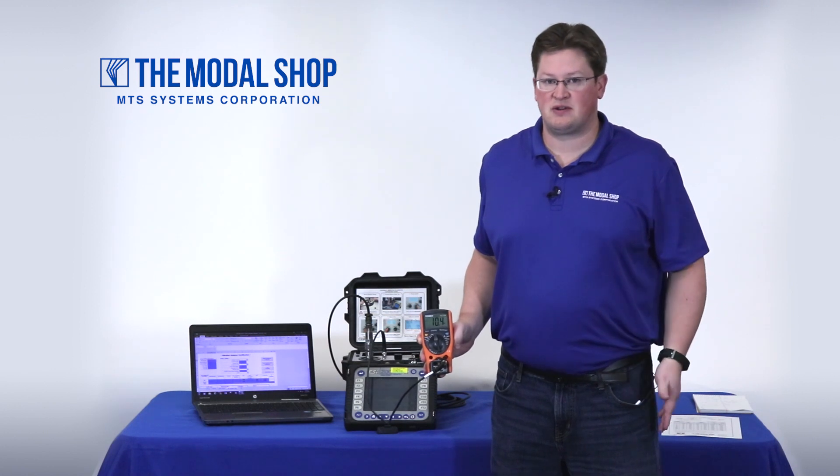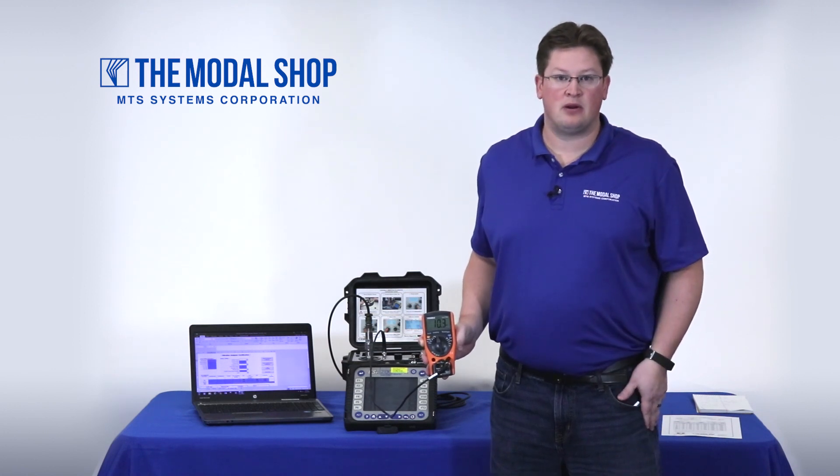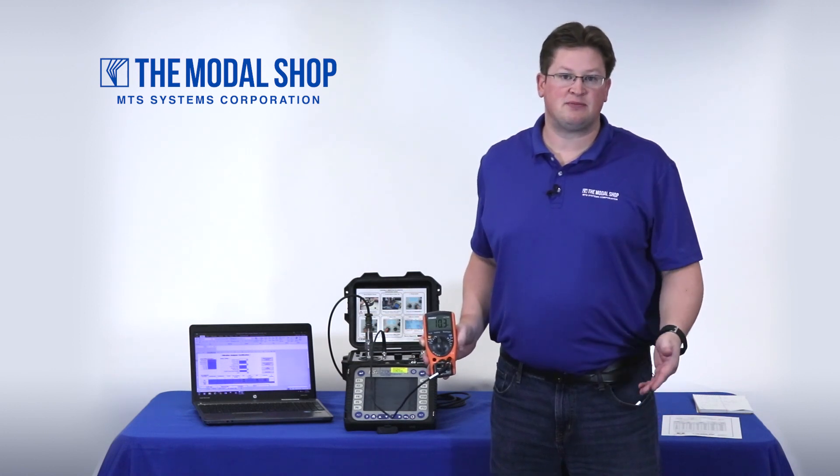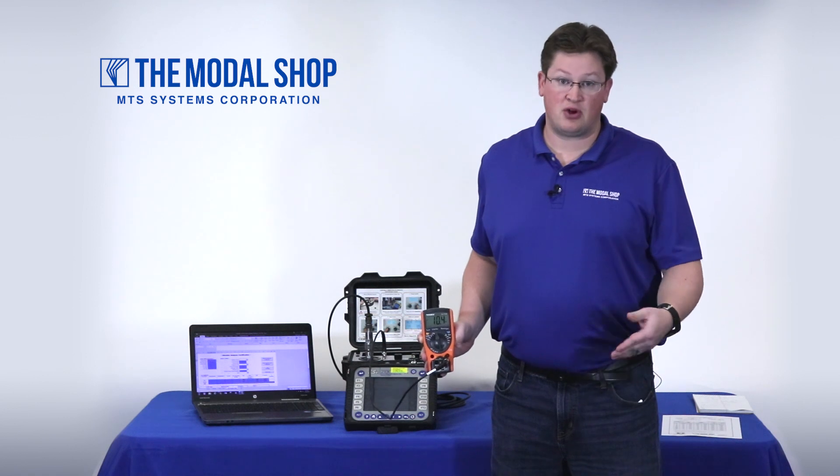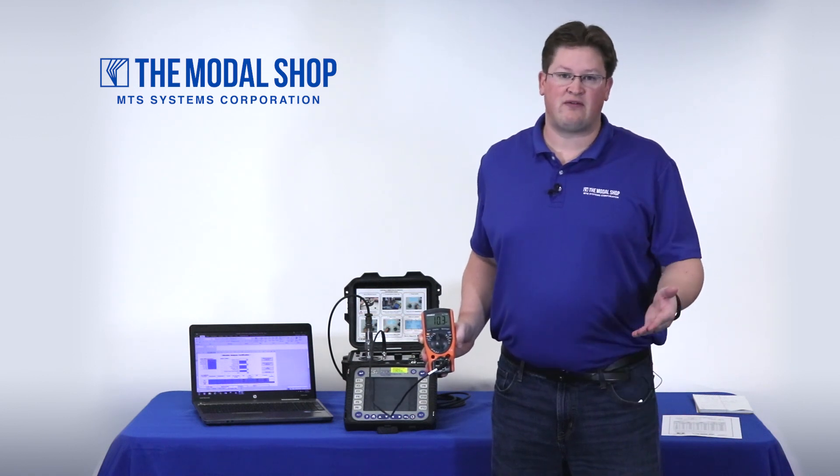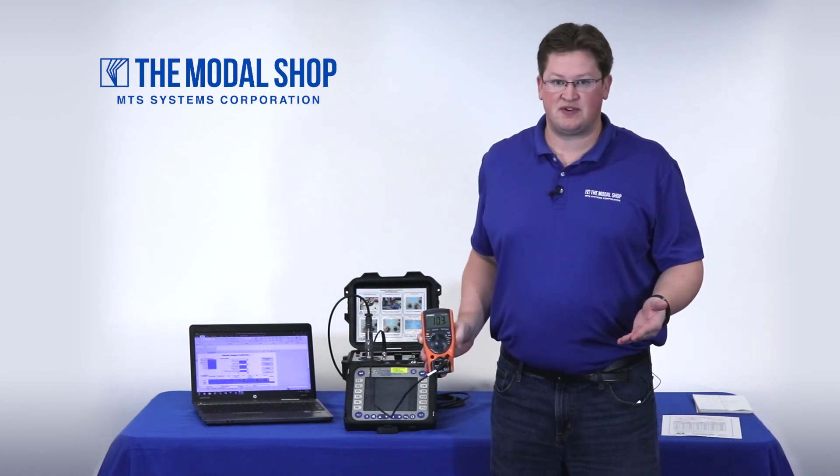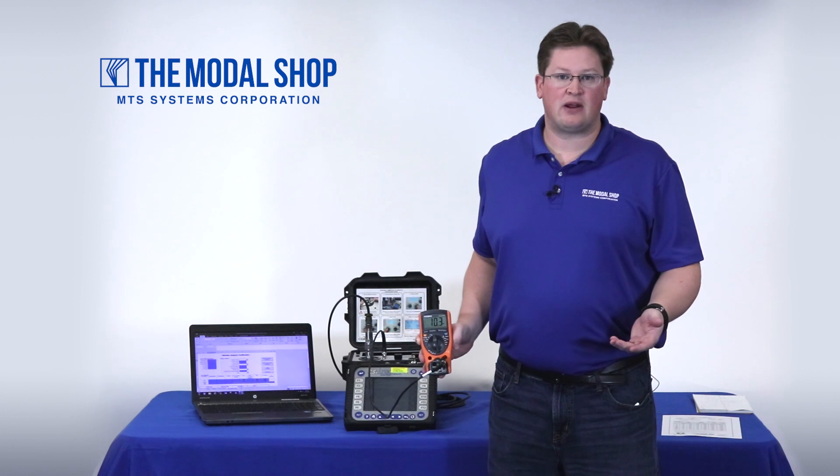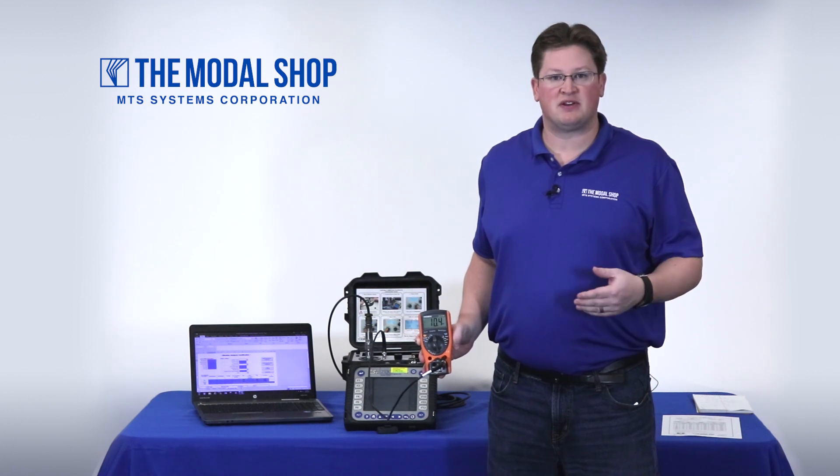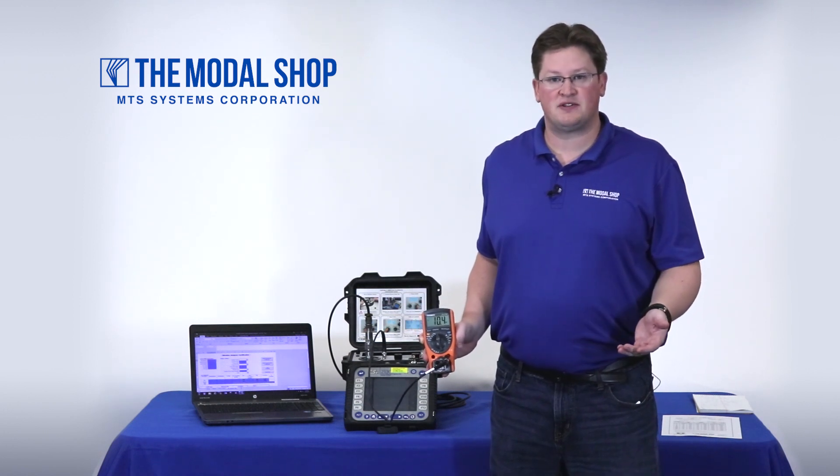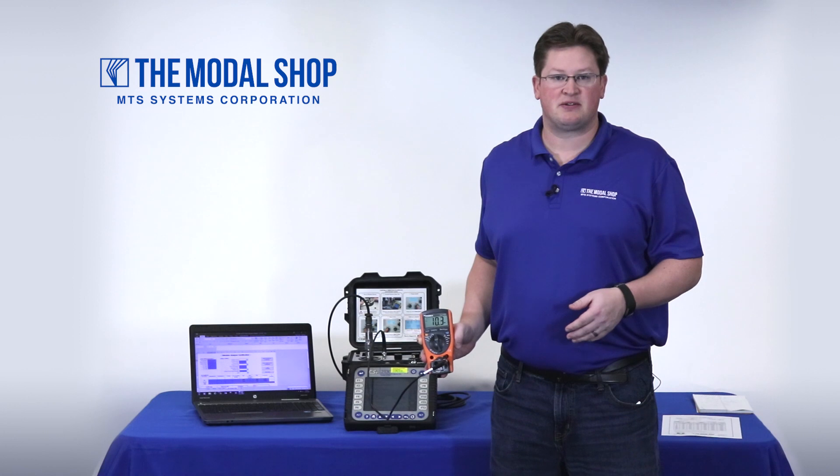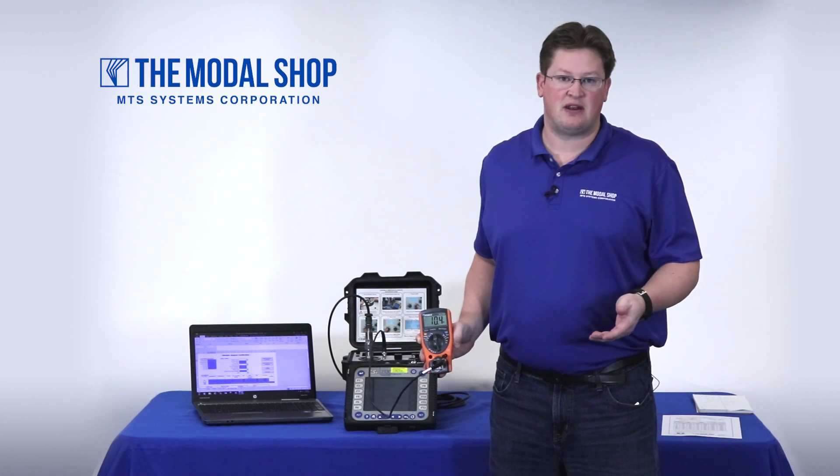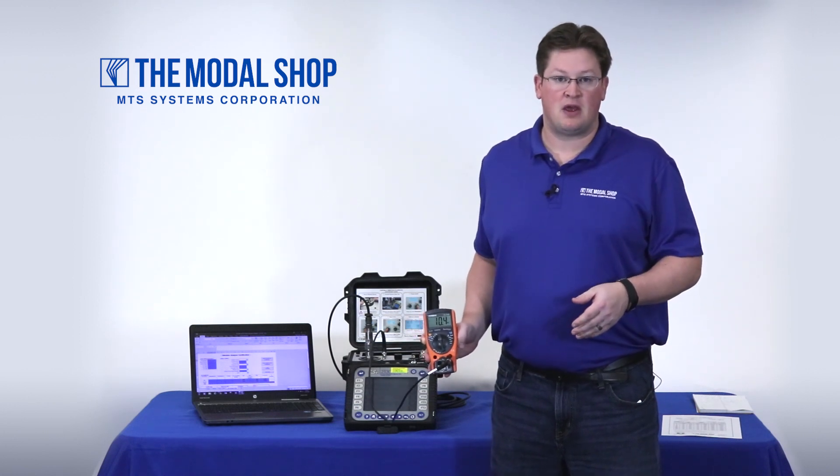Two key innovations about the Portable Vibration Calibrator make it possible to calibrate a Portable Vibration Analyzer. One innovation is the accuracy. The accuracy of the 9110D is plus or minus 3 percent from 10 hertz to 10 kilohertz and plus or minus 5 percent from 5 hertz to 9 hertz.